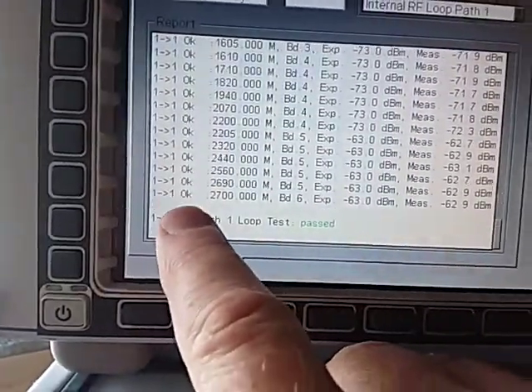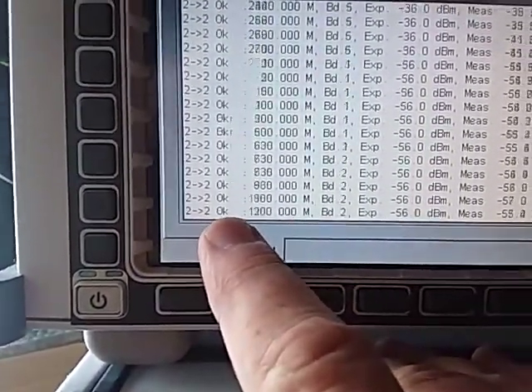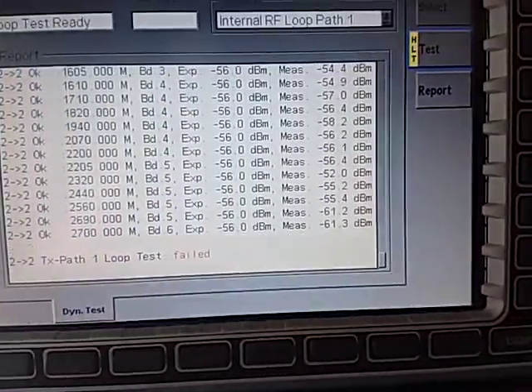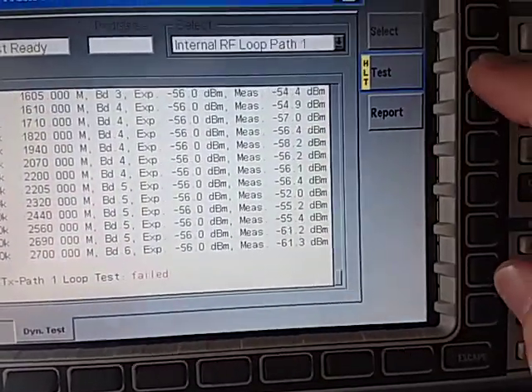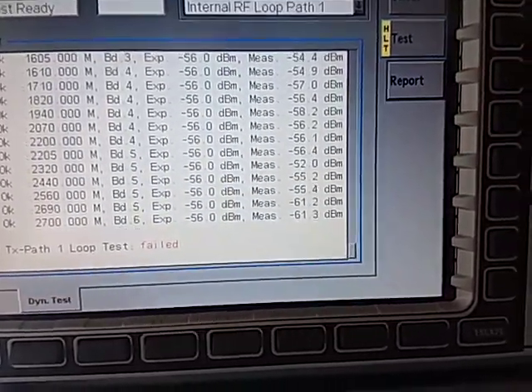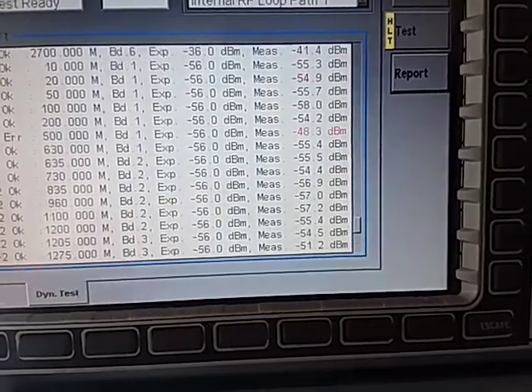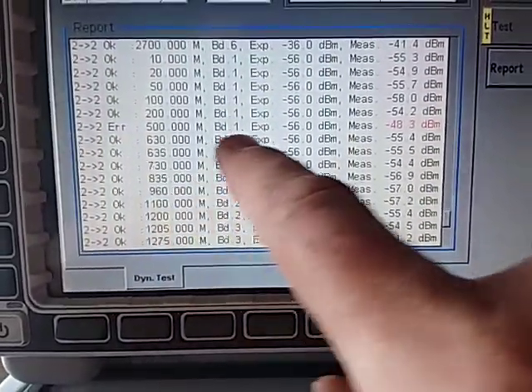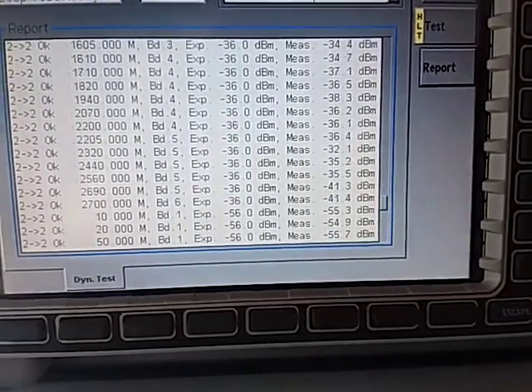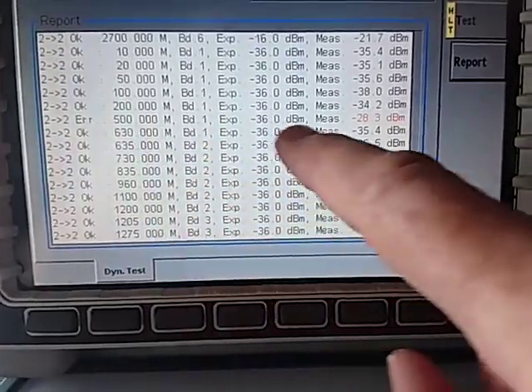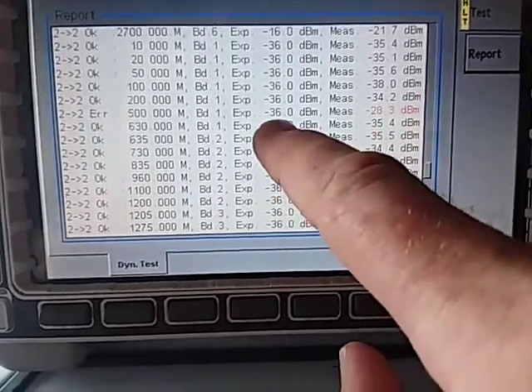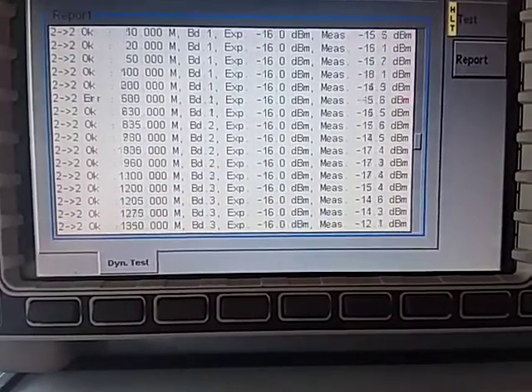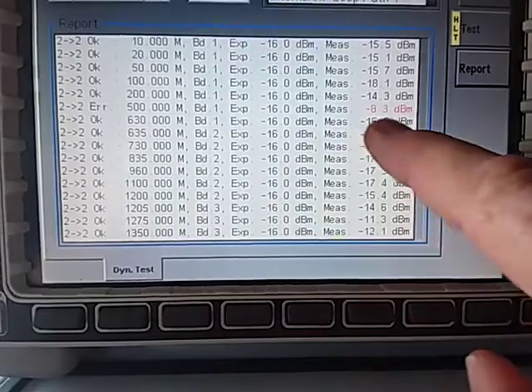This is path one. Now if you want to do path two, you press the continue and it will do the path two. Pretty sure there's only two paths and it's telling us here that this has failed on mine. If I hit report I can see it's failed on one frequency here about 500 megahertz. What else has it failed at? It's failed again at 500 megahertz at this frequency, at this power level. I bet we find another 500 megahertz, yes, and another 500 megahertz.